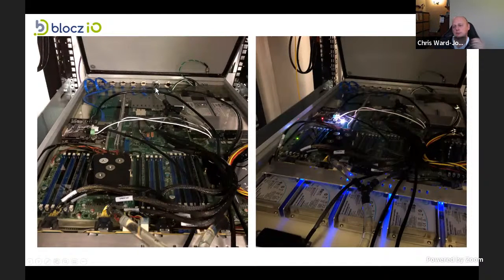There's two ways of doing this. We can have a heat exchanger in the box, or outside of the box. But the point is, we extract the heat from the hottest components. So the liquid in the unit acts a bit like a thermal battery. We pick up that coolant, take it across the hottest components, and then directly from the hottest components, take it out of the box and straight into a heat exchanger.